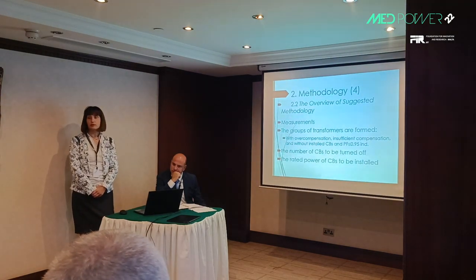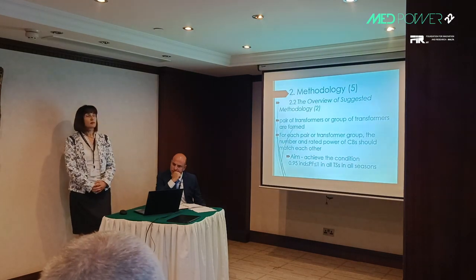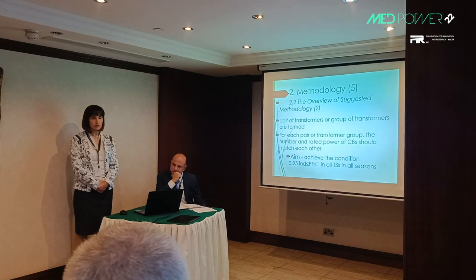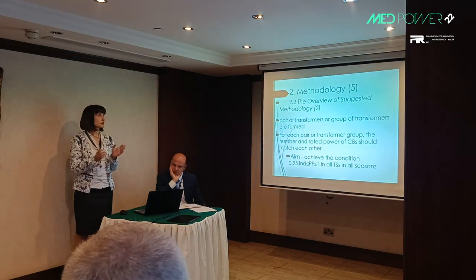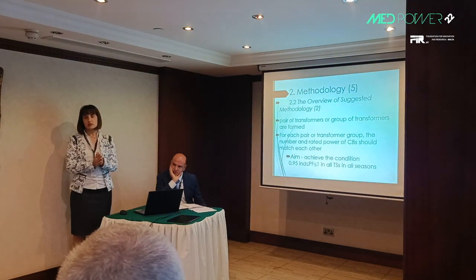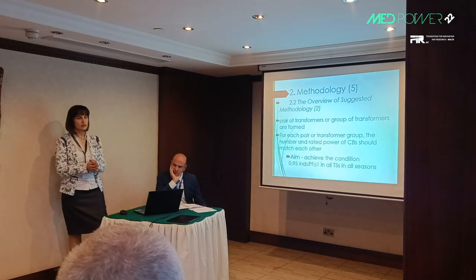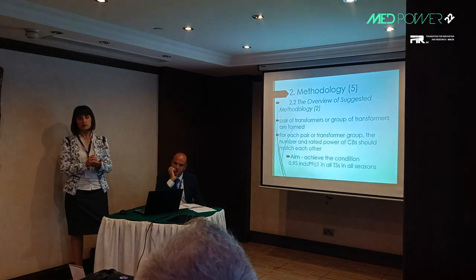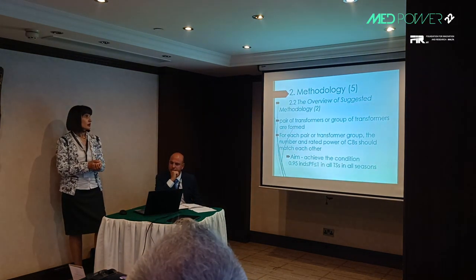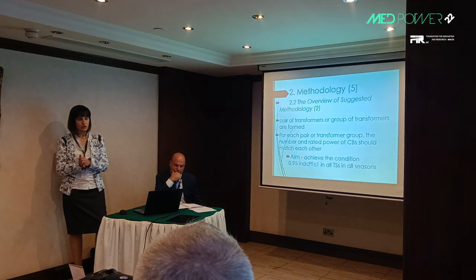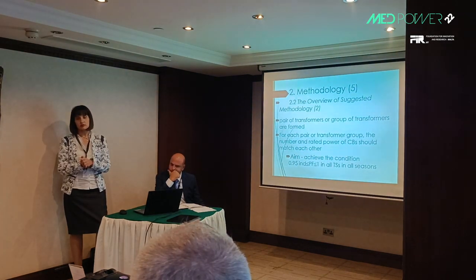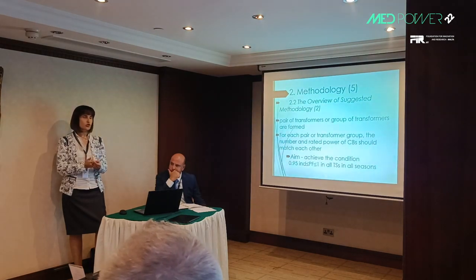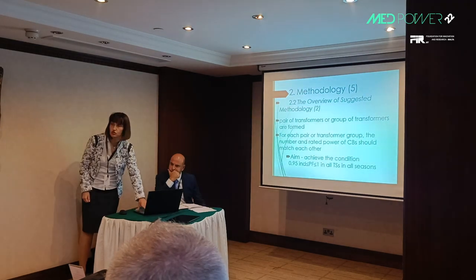The aim of the suggested methodology is finalized by making groups of transformer substations in which overcompensation is noticed, noting the number and rated power of capacitor banks previously installed, and identifying how many should be uninstalled. Another group consists of transformer substations where capacitor banks are not installed and where new ones should be installed — either new units or those uninstalled from substations with overcompensation.